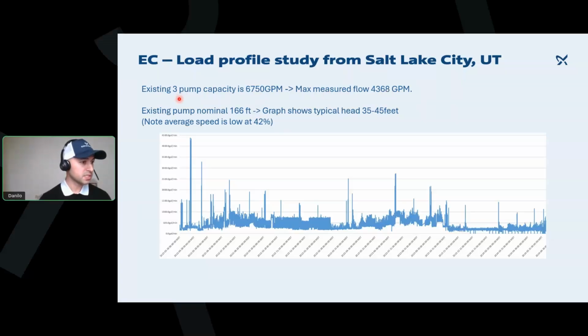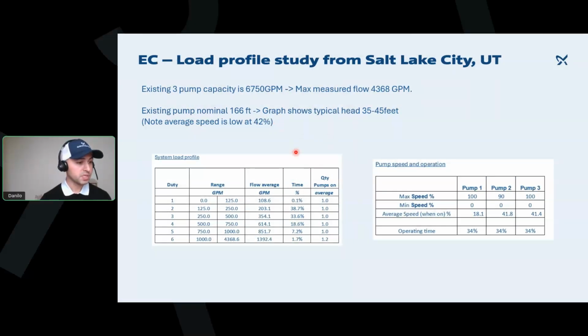And the existing pump nominal head, right? It had about 166 feet on its nameplate. But if we look at the graphic, it will show that the typical head was actually, instead of 166, only 35 to 45 feet. Also noting the average speed of the pumps, so these pumps are on VFDs, right? You're noting that the average speed is 42%, and I have some more data where we can see their load profile.